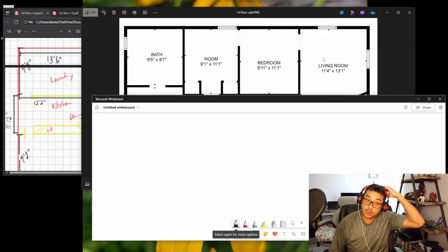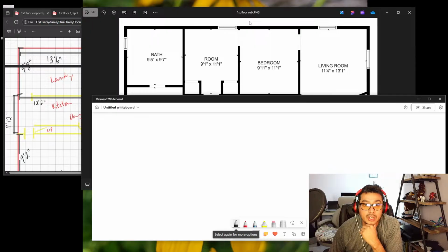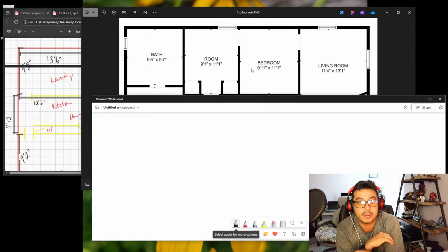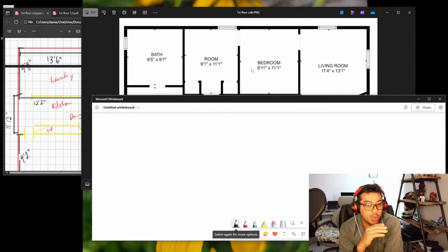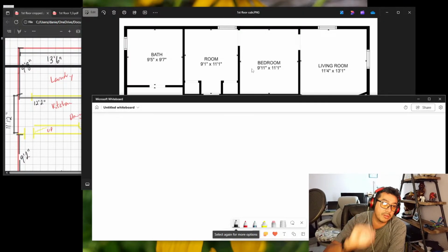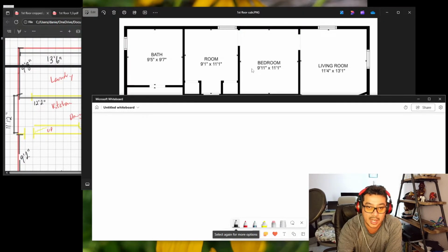I'm going to quote this the very long way so that we have extra pipe. I want to have extra pipe and extra communication wire. I'm not sure how much space we actually have in the basement to run the. I would rather run the line sets and everything downstairs through the crawl space or basement and then jump up the drywall. It'll look prettier. Either way, this is not pretty because it's a finished home. And no matter what, we have to cut into some drywall.